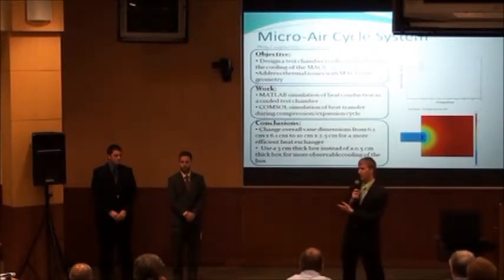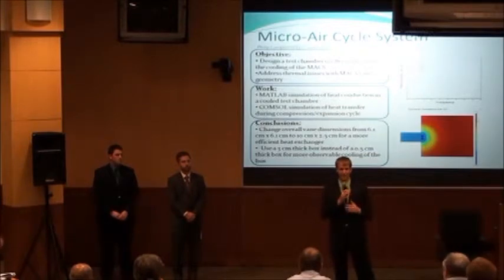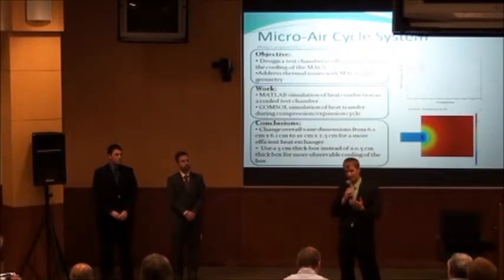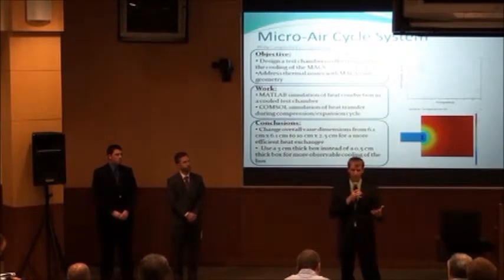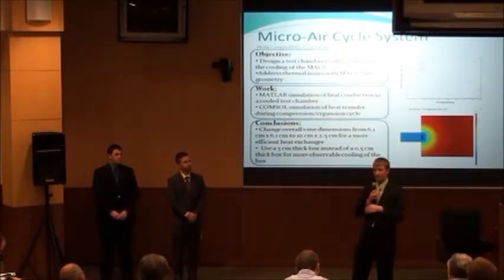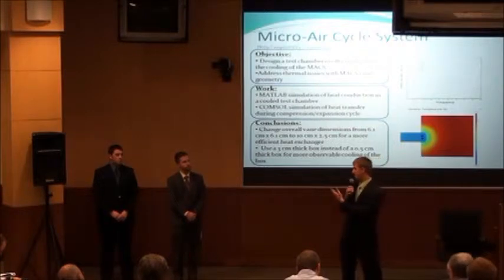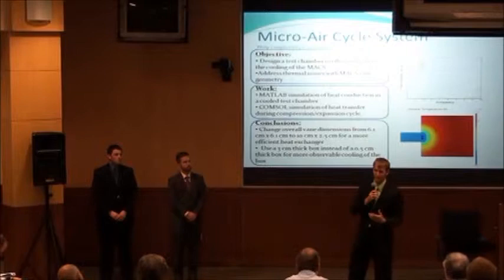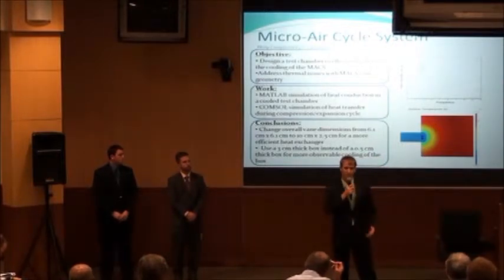The other problem was understanding what's actually happening inside the vanes as they compress and the heat is pulled out, and as they expand, the air is then at a cooler temperature than the plates, so the heat starts dumping back into the air. That was Alex's main work this semester, writing a COMSOL model that solved that. One image of that is behind us.